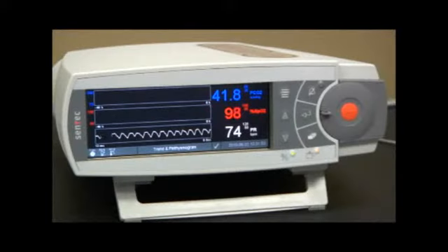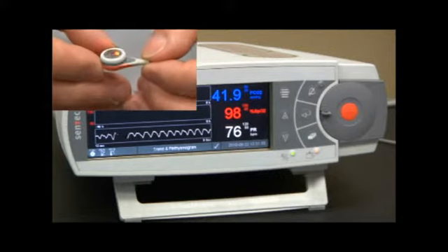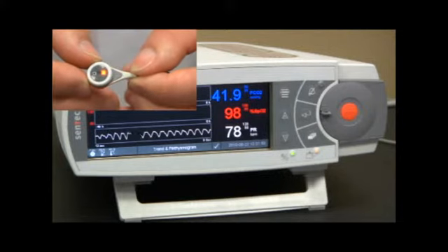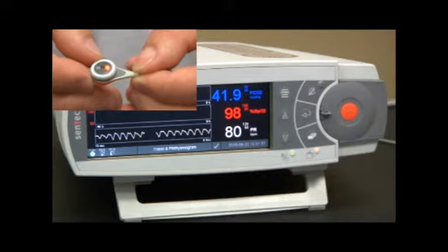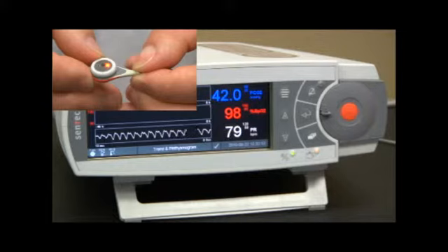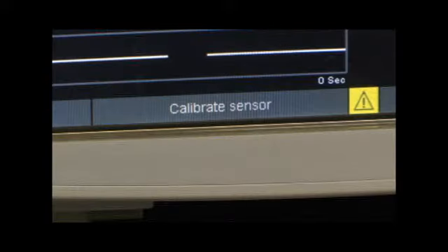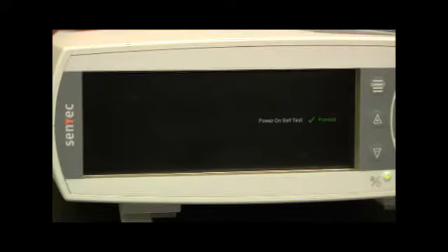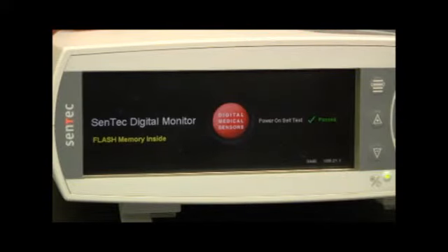Sensor calibration. Your Sentec digital monitor includes a state-of-the-art V-Sign sensor providing measurement of transcutaneous PCO2, oxygen saturation, and pulse. PCO2 measurement is performed utilizing a patented digital electrode providing fast and reliable PCO2 readings. The digital electrode requires periodic calibration as displayed in the status bar window. When the unit is powered up, the Sentec monitor will indicate that a calibration is necessary.